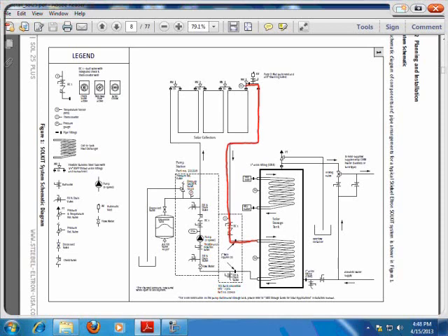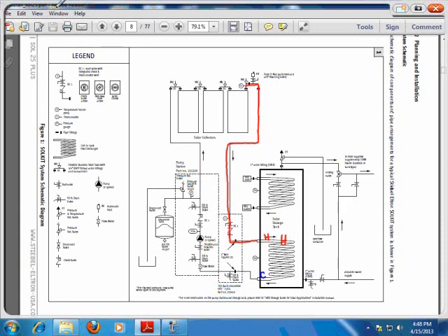So here is what happens. Notice the hot water comes in on the top side and it leaves, we'll call that the cold side, on the bottom. And the reason we want that differential is we want the hot water on the top and we want the cold water that's exiting. That's really not cold, but considering what we have here, hot water rises, we want a thermal difference between the two. So what we want is to try to cause a stratification of the water between these two layers. So keeping the hot water on the top side of that coil, having the cold water leave is what we want.